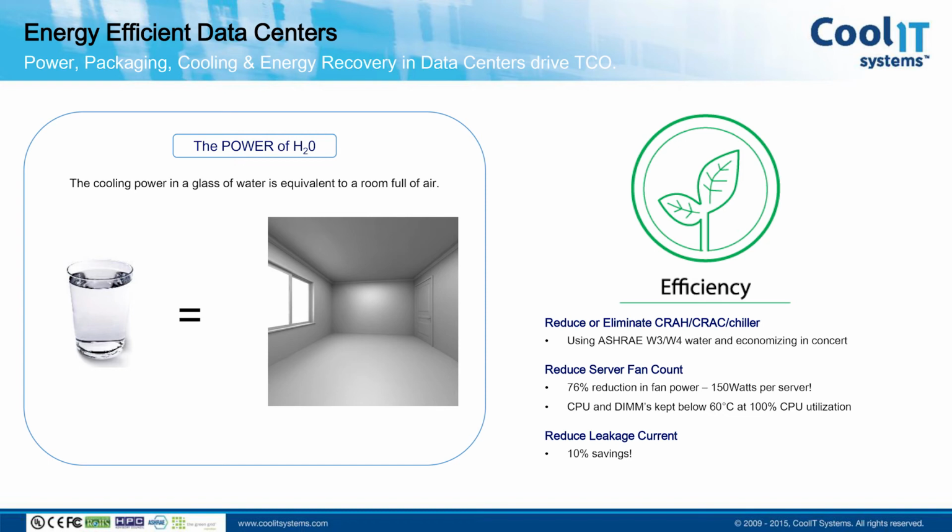Very cool stuff. Now, when we're talking about cooling for performance, we definitely see you're looking for performance per watt, and definitely an advantage to reduce the server fan count, which you can essentially eliminate all of them, right? It depends which cooling technology you use. You can potentially. You're going to need some air probably to cool the memory if you're not going to go that far. A little bit for the ASICs on the motherboard, but that's not a whole lot. So you figure about a three-quarters reduction in fans? That's usually it. If you put GPUs in the mix, typically it's closer to 80. But that's it. It's usually between 65-75% of the energy is going to be evacuated through the warm water.